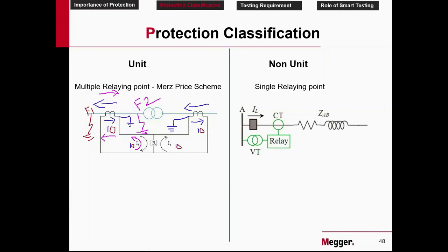This CT provides current and the VT provides voltage. And we divide voltage by current. We get impedance, Z. So we are using only one measurement, that is called as impedance measurement. Hence we call this as single relaying point, because we are only measuring only one parameter.